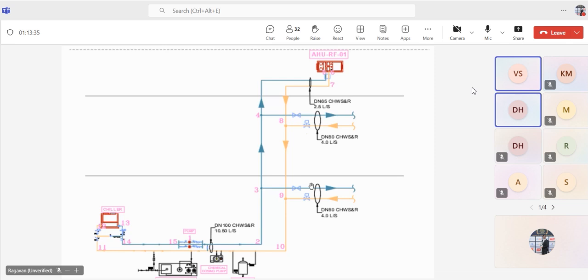So usually when you do the pump set calculation, in that situation, for friction losses, what flow should we consider, the entire area's flow? No, this is what I said: there is a coverage area. In the hydraulic calculation, if you go to the fire hydraulic software, a chart will come. When you go through the input data, I think the last one is the coverage area, then each sprinkler's coverage area, and the flow rate.